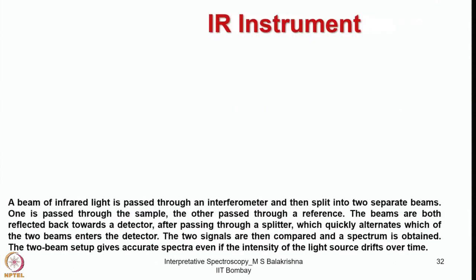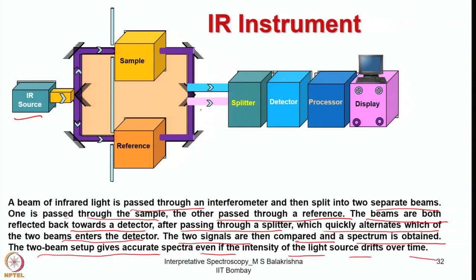A typical IR instrument works as follows: a beam of infrared light is passed through the interferometer and split into two separate beams — one passed through the sample and the other through a reference. The beams are reflected back towards the detector after passing through a splitter which quickly alternates which of the two beams enters the detector. The two signals are compared and a spectrum is obtained. The two-beam setup gives accurate spectra even if the intensity of the light source drifts over time.